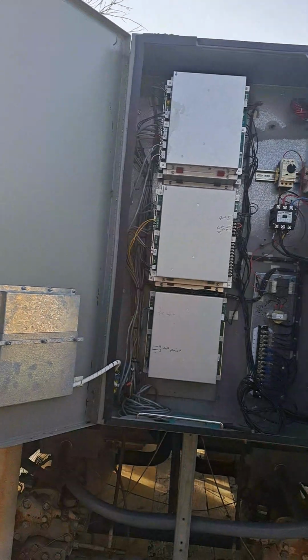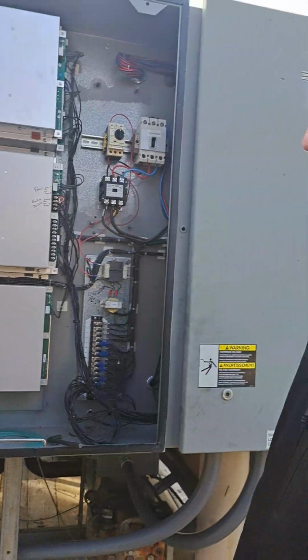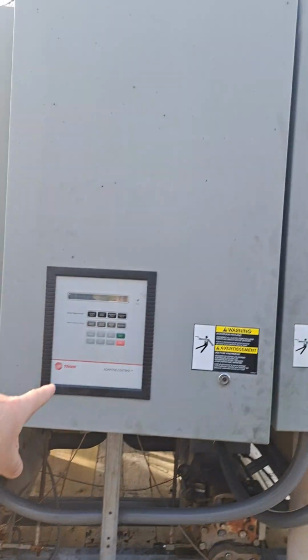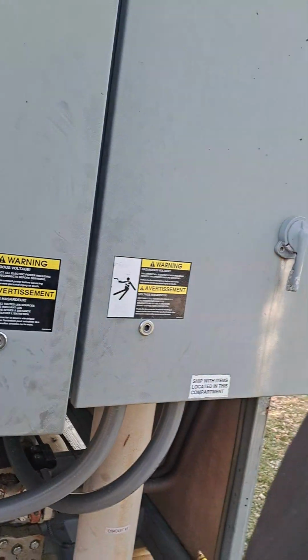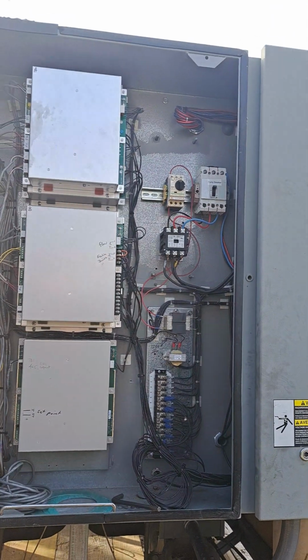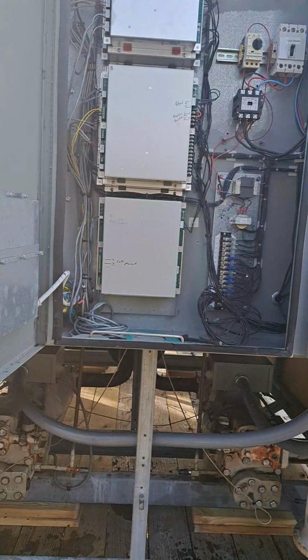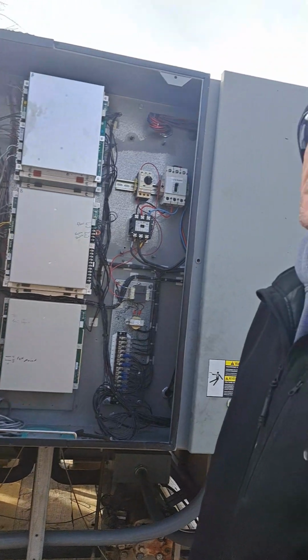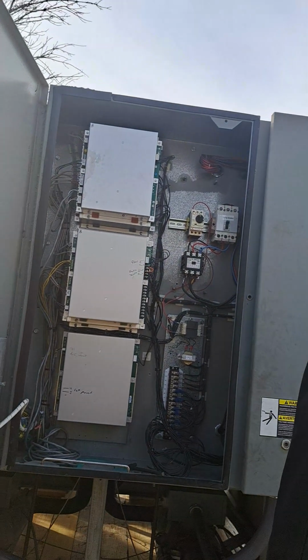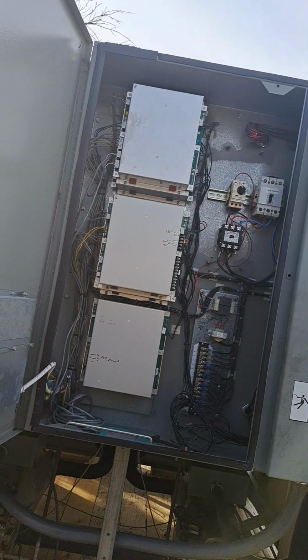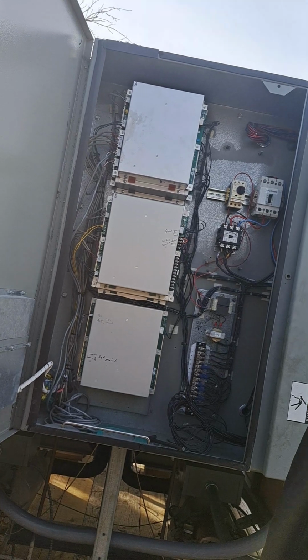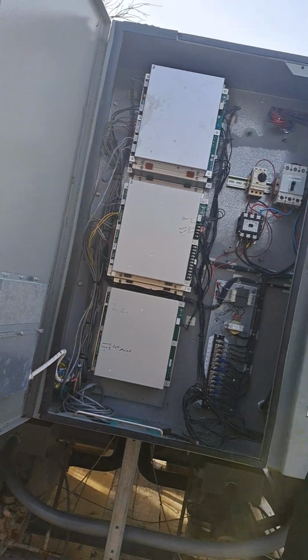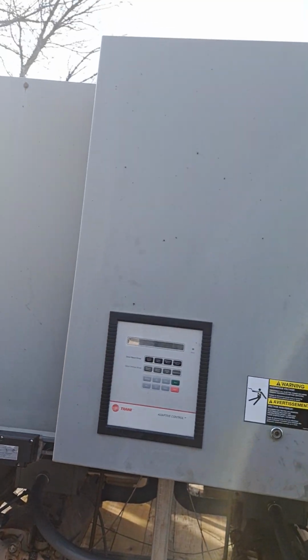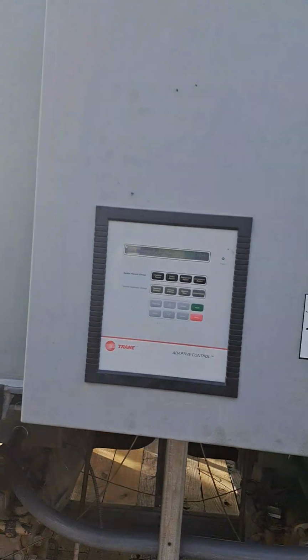So let me ask this real quick. If we had to shut it down, we first hit stop, and then we open it up and turn the pump off. Correct. Okay. And then when you start it back up, it's the reverse. You start the pump first, and then start the chiller up. Yeah, you guys really should put a flow switch on this thing if you're going to keep it. And if we were starting this, which we're not, we just hit auto? Yep, just hit auto and it'll go through a startup sequence.